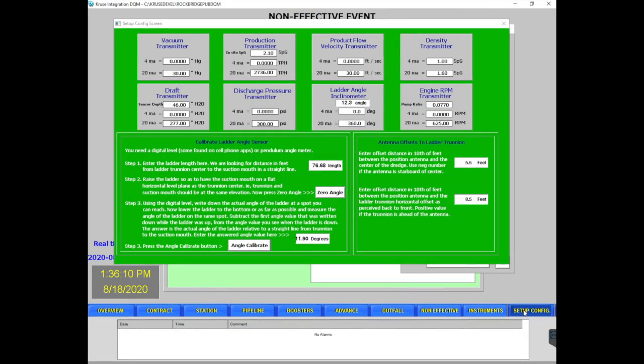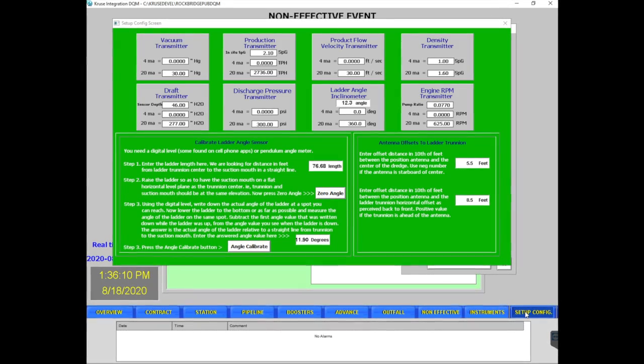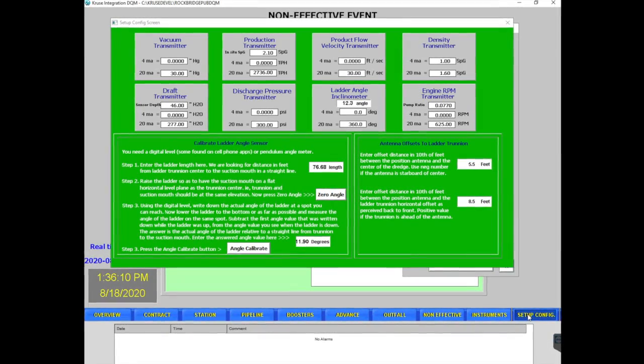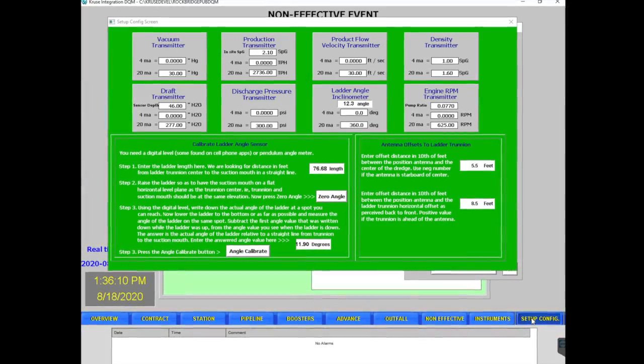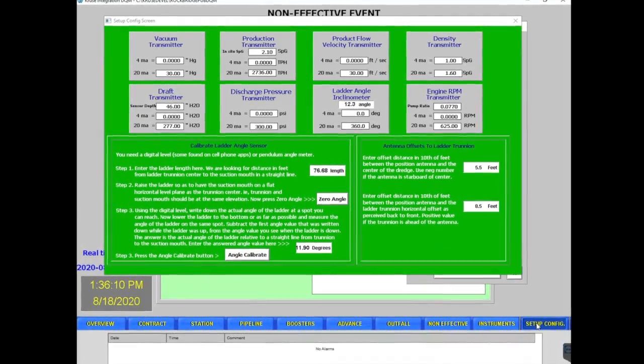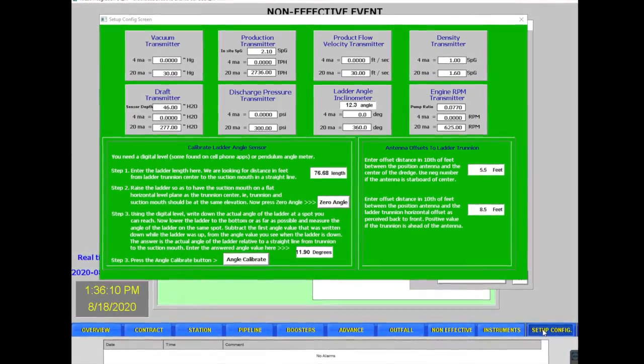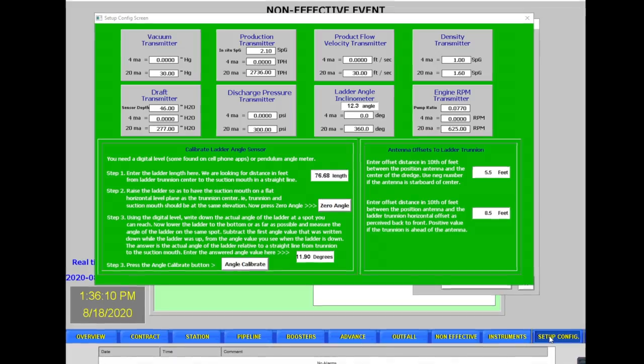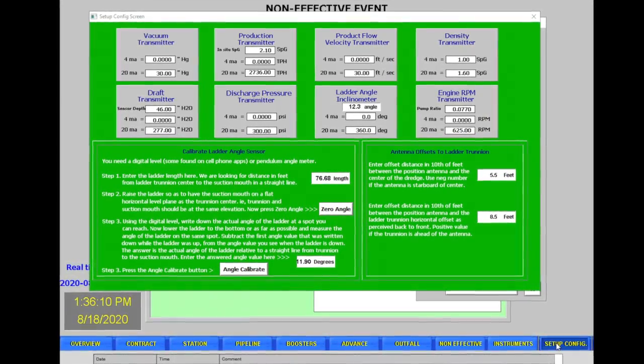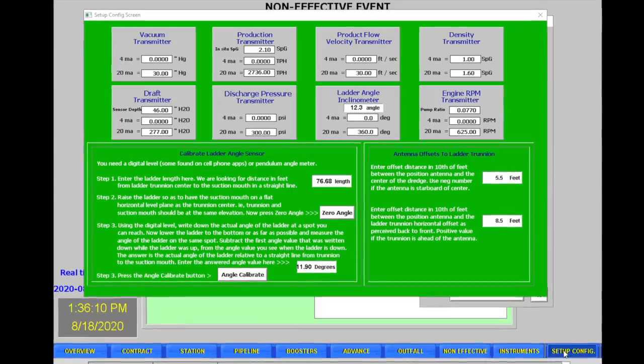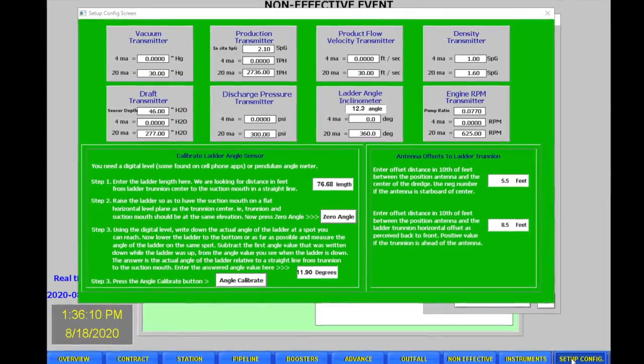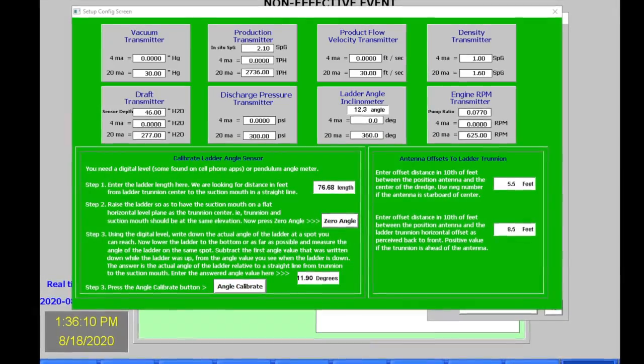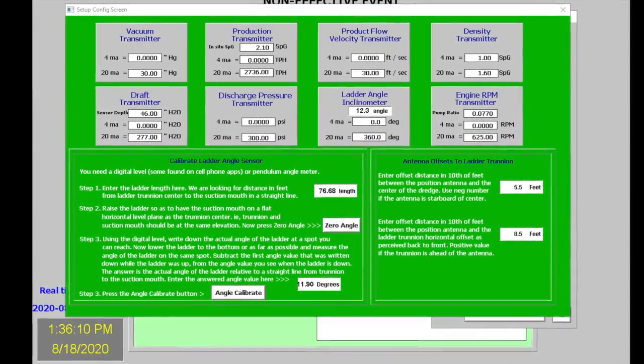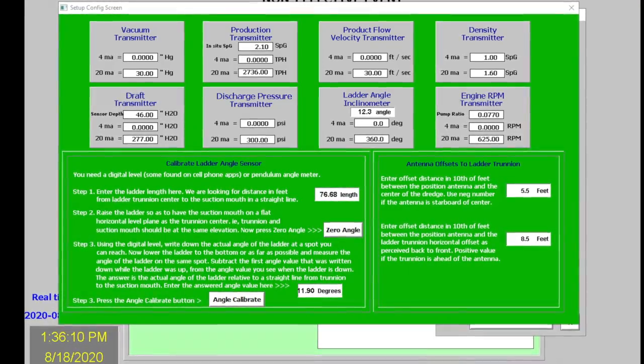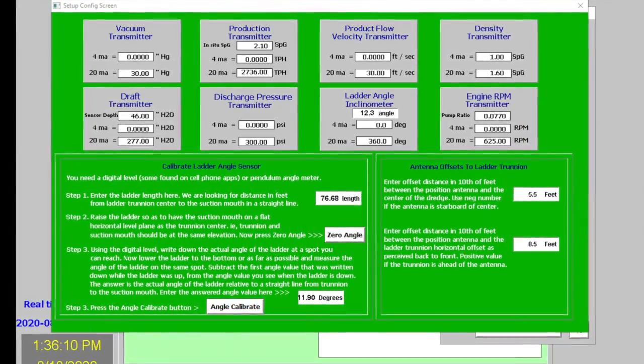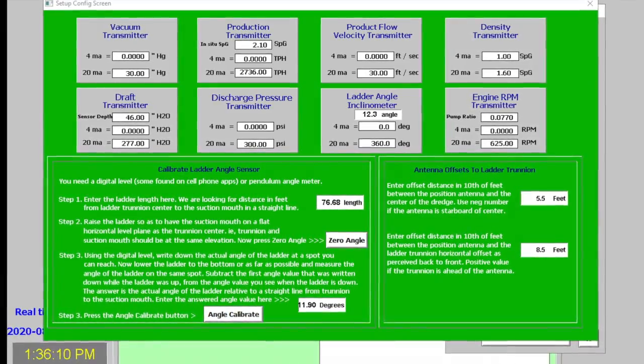The final screen on here is the setup screen. This is used for you to calibrate your instrumentation. Most all instruments that are 4 to 20 milliamp off-the-shelf instruments have a scale on them or a tag that specifies what their range is from 4 to 20 milliamps. So if you ever change any instrumentation, this screen is where you would go to update your calibration. The other thing you do on this screen is put in your antenna offsets, and you can calibrate your ladder angle sensor on this screen.